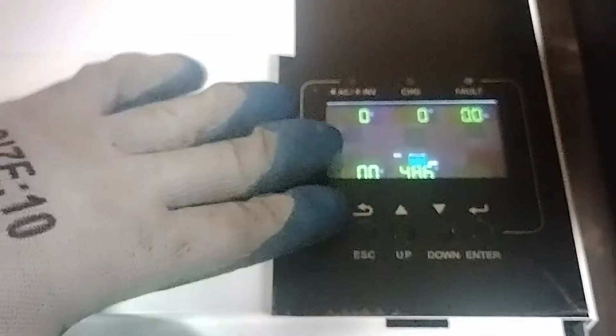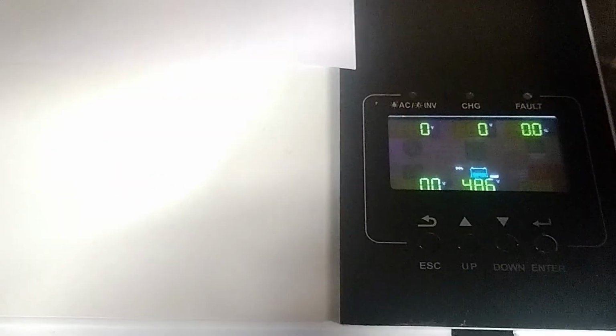But as soon as the inverter goes off, you'd have to do a reverse, or it will give you error 04 and 20, and you'd have to go back to AGM and do a reset, moving it back to lithium. So that's the only downside with regards to using the Hope battery with the Growatt inverter itself.